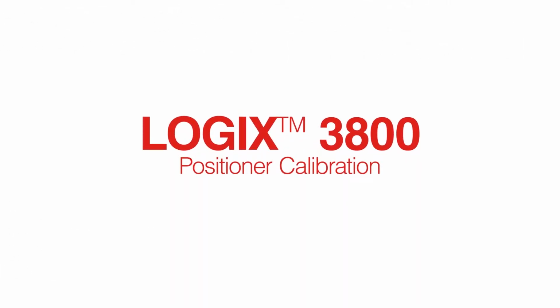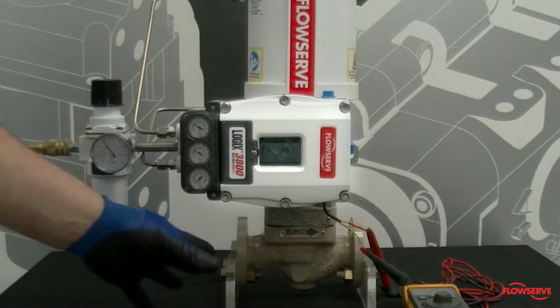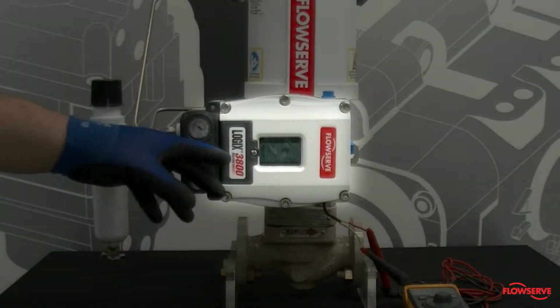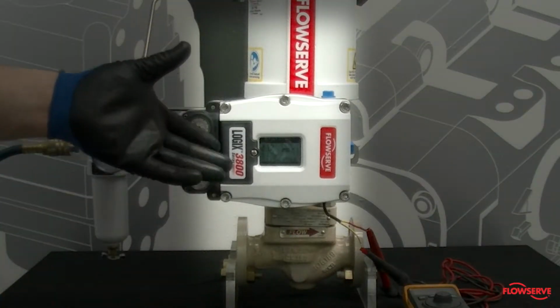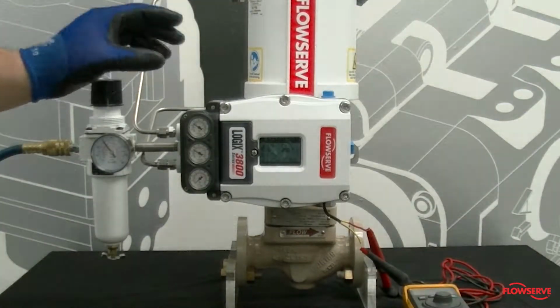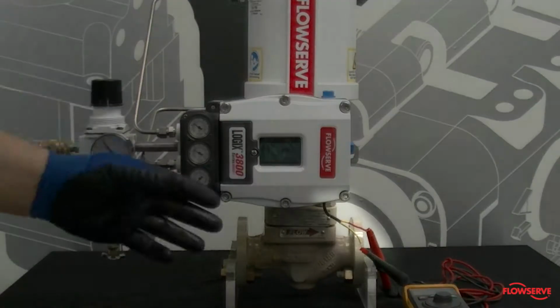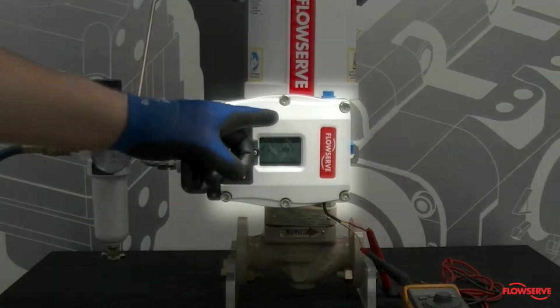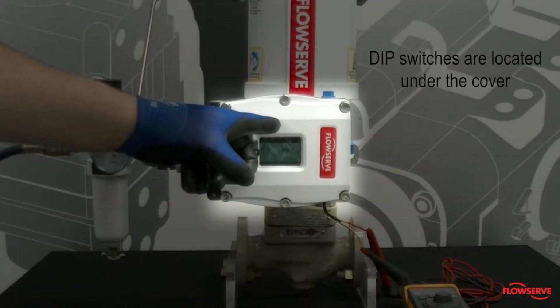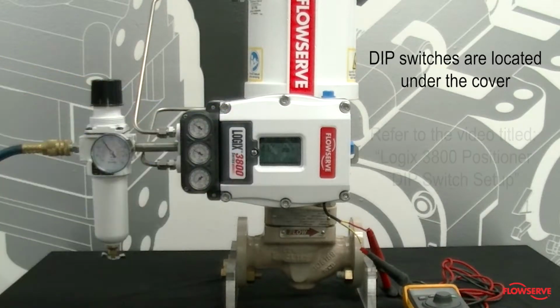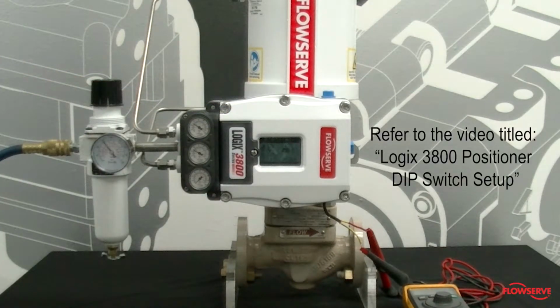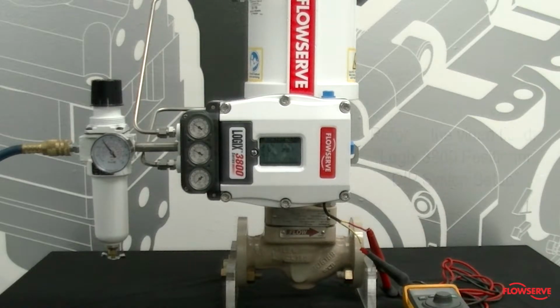This video shows how to calibrate a Logix 3800 positioner. After the positioner has been installed, it must be calibrated. The positioner will need to be mounted on the valve, fully tubed, powered, and all the dip switches set per your valve configuration. Refer to the video titled Logix 3800 Positioner Dip Switch Setup to set the dip switches.